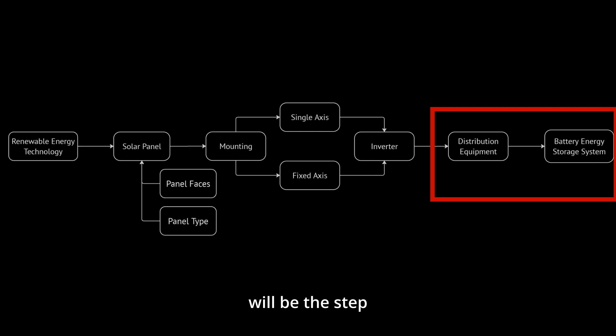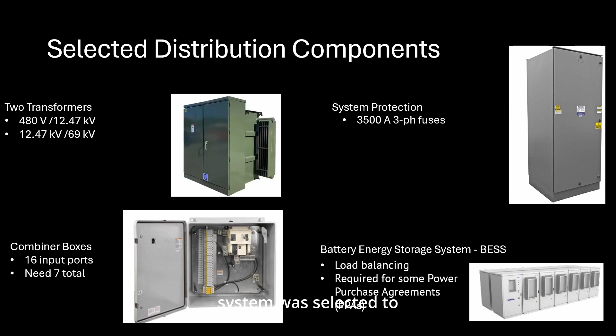After comprehensive research, the distribution components that were selected are a step-up transformer of 480 volts to 12.47 kilovolts and another step-up transformer of 12.47 kilovolts to 69 kilovolts, which is the local voltage level. In addition to that, combiner boxes as well as 3,500 amp three-phase fuses were chosen for system protection, and a battery energy storage system was selected to collect power over time.